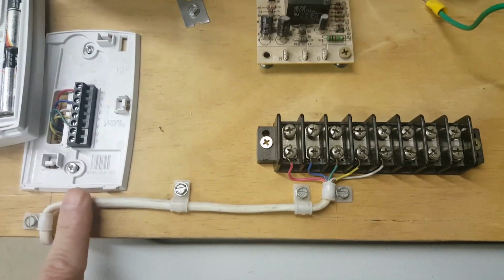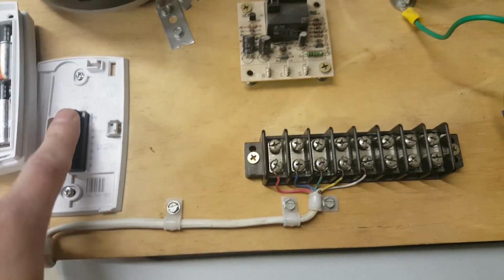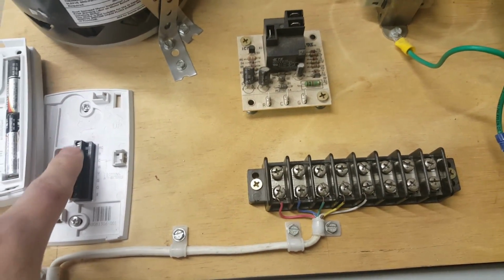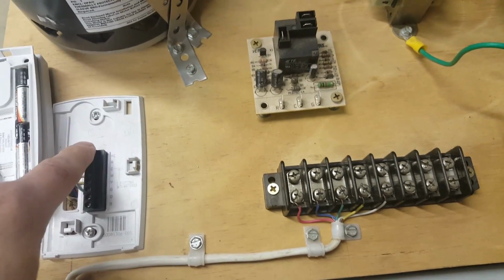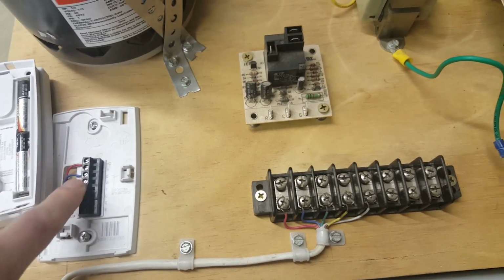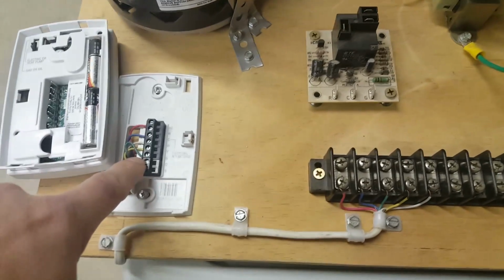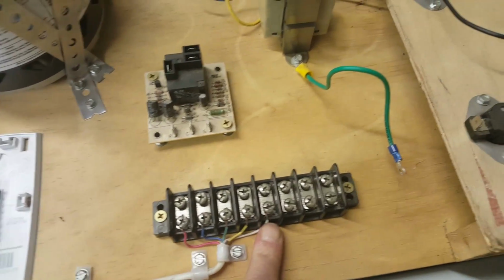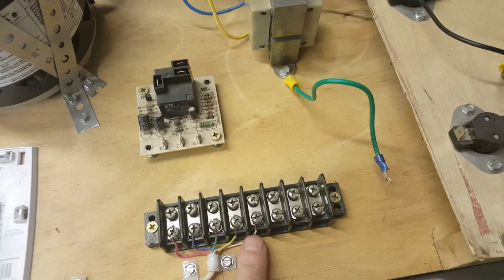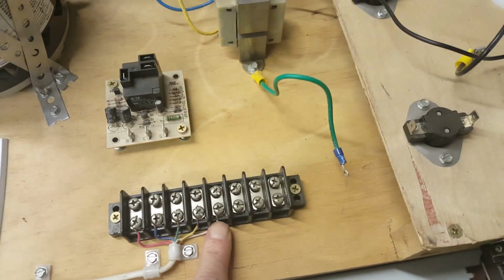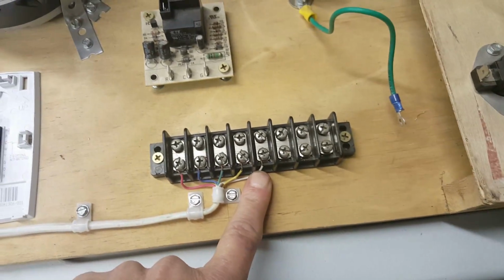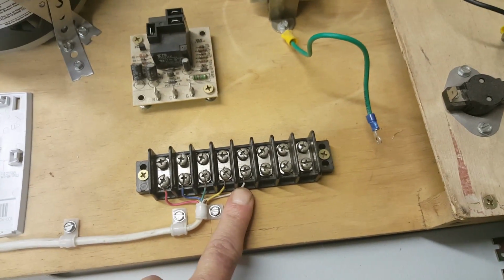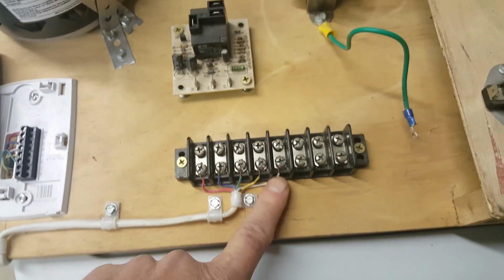And it'd be the same way in the heating mode. If you're calling for heating, then your R wire stops here, but when the thermostat calls, it closes the switch to the W circuit, comes out here and energizes W. G for the fan circuit is not energized in the heating mode. The heating relay operates the heating elements and the fan in the heating mode.